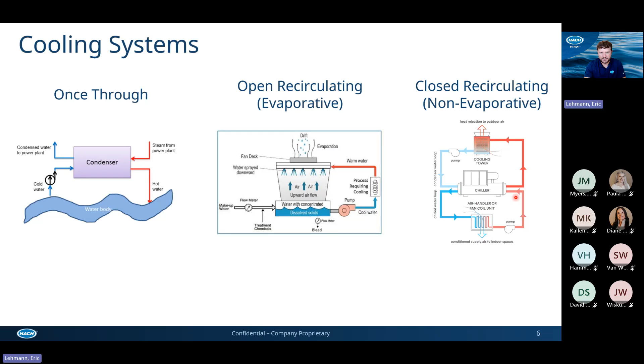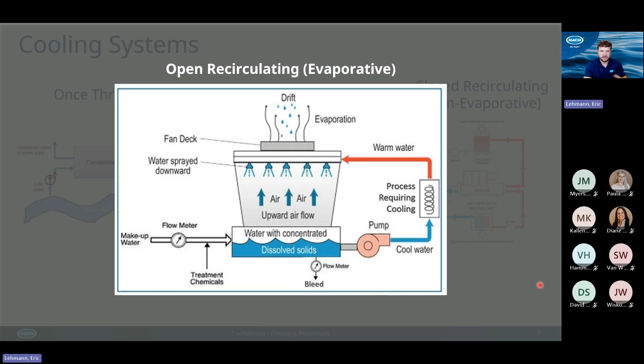The cooling system that we're going to focus on today, and this is primarily what we see in industry, is an open recirculating evaporative type cooling tower. So the way this operates is you have the warm water coming in, that water gets sprayed down. You have upward airflow. There's a material called fill in these cooling towers. So you have upward airflow where that warm water is starting to evaporate out. It's concentrated down at the bottom with the dissolved solids, and then it's continuously pumped into a circular type motion. Now, with this evaporation, they're very effective, but the evaporation creates a lot of challenges when it comes to controlling them and controlling the chemistry of the cooling tower to make sure they work effectively.